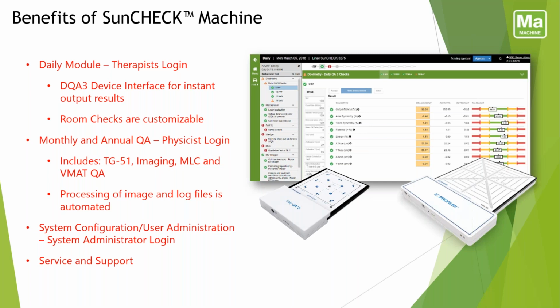For the monthly and annual QA, they're accessible through the physicist logins. They include all the TG142 tests, as well as TG51. All imaging, MLC, and VMAT QA tests are all included. The processing of image and log files is automated and really works out pretty well. And the system configuration and user administration, again, is all controlled by the system administrator login, which in our install, I reserve that role.